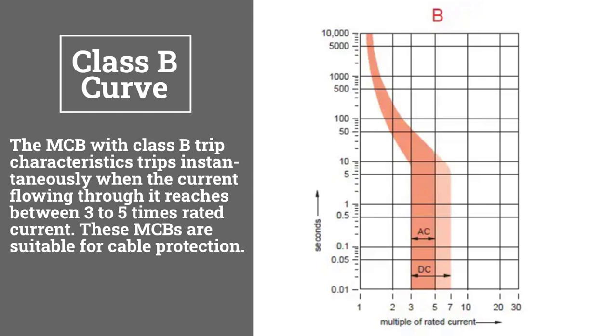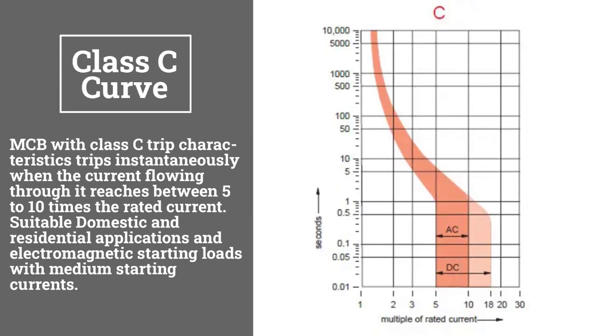Class B has a tripping curve of 3 to 5 times the rated current and it's suitable for cable protection. Class C has a tripping curve current of 5 to 10 times the rated current and it's suitable for domestic and residential applications.